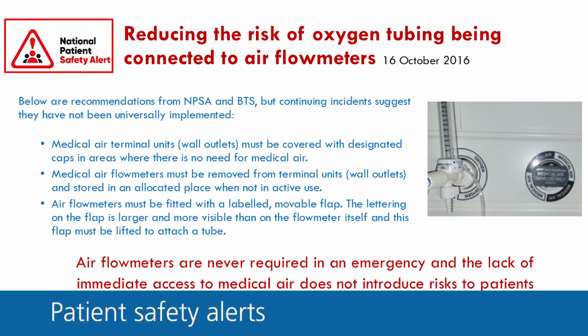There are 3 recommendations from the National Patient Safety Agency that must be actioned. Medical air terminal units, wall outlets, are covered with designated caps in areas where there is no need for medical air. Medical airflow meters are removed from terminal units or wall outlets and stored in an allocated place when not in active use. Airflow meters are fitted with a labelled movable flap. In an emergency, airflow meters are never required, therefore the lack of access to them does not introduce or increase risk to patients.